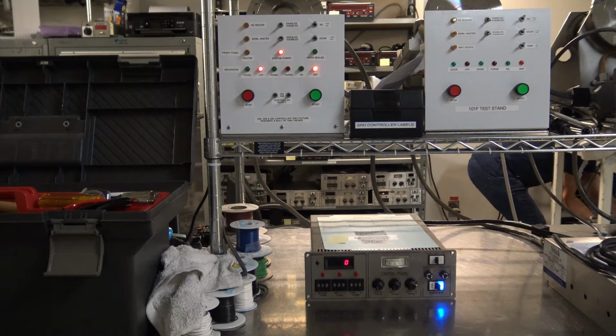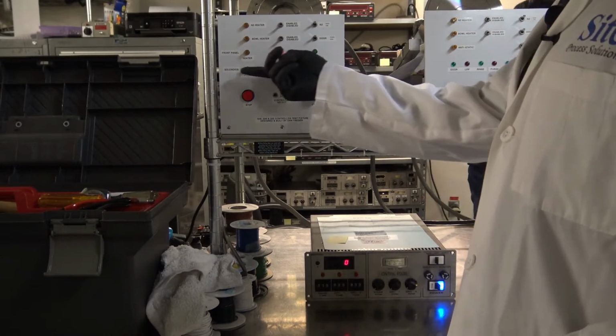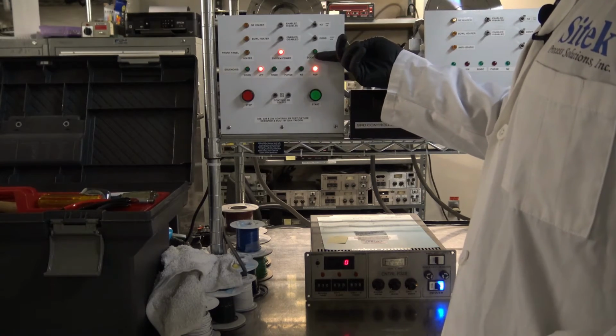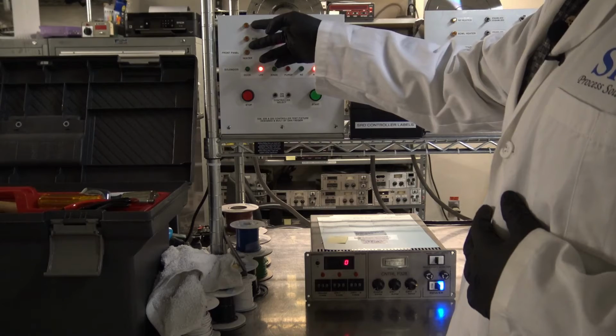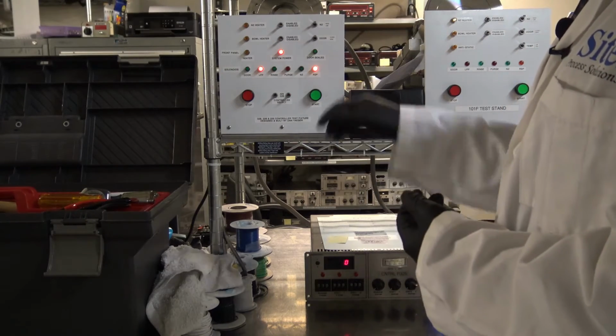We will be running expedited test cycles for you today, so we aren't filming all day here. We're going to be doing a 30-second rinse, 30-second dry 1, and 30-second dry 2. Before we get started, I'm going to show you our test assembly. This bottom row of lights shows which solenoids are turning on. Here we have the lights that are symbolizing what would be on the front power panel of their ST, and then we have our 2 bowl heaters on the top left here. Let's go ahead and begin.